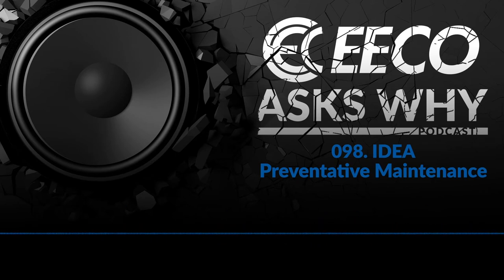A lot of that involves site walks, so bringing your preventive maintenance company on site to actually walk the facility. Understand if we're going to be testing in certain areas, can we hook our test equipment up? Do we have a known good voltage source? Do we have to bring generators on site? That's all fundamental logistics information. Do we have badging? Are there special PPE requirements to work in this particular facility? That's all high level discussion that comes out during a pre-planning meeting and initial site walk.